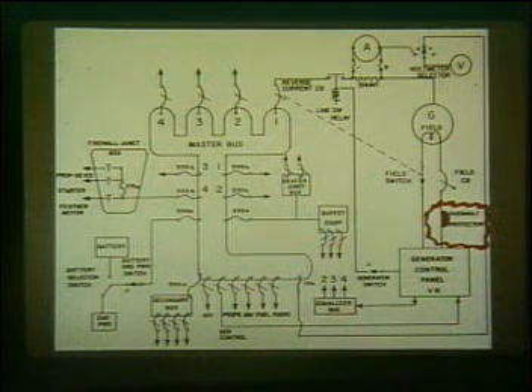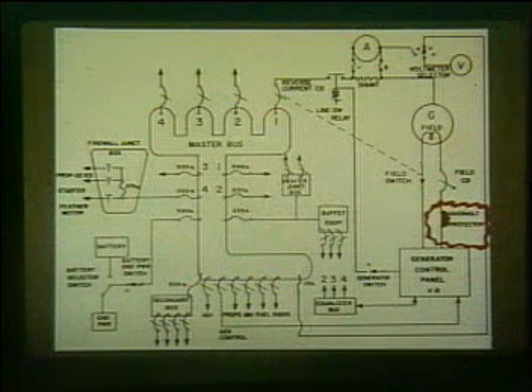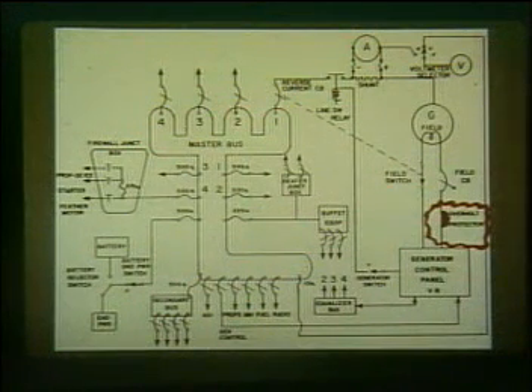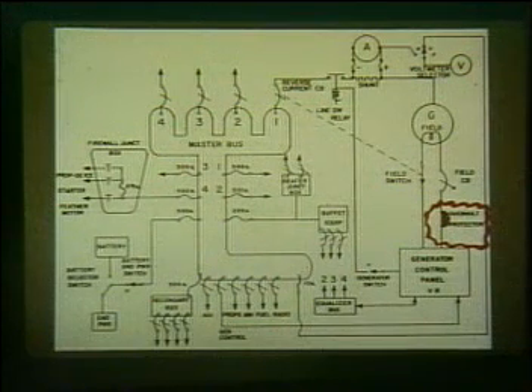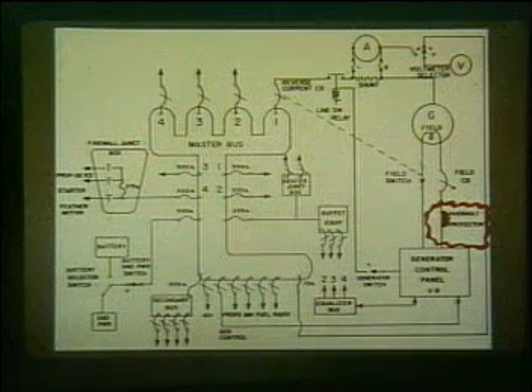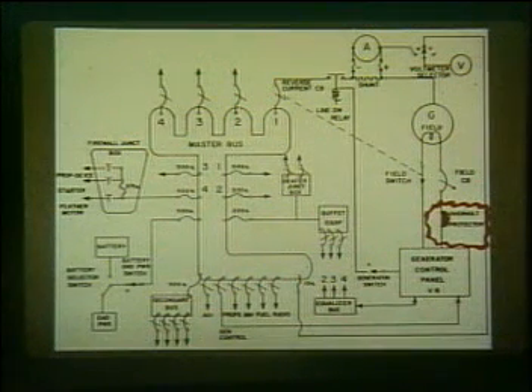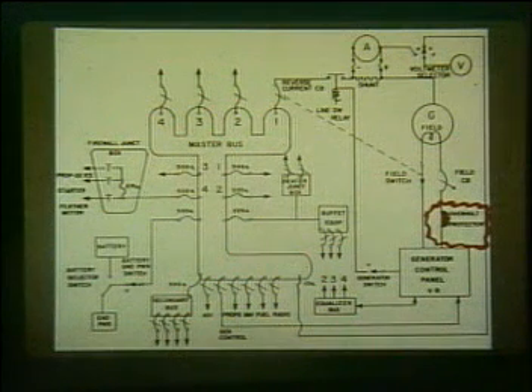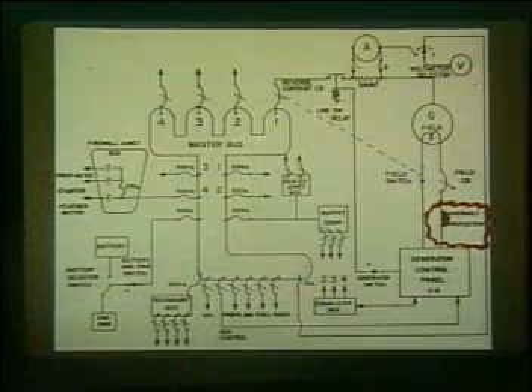The overvoltage protector located in the main junction box will trip and remove the generator from the bus should full field voltage occur. An application of full field voltage could cause a bus voltage in excess of 70 volts. The overvoltage protector, when tripped, will also open the generator field, thereby rendering the generator inoperative.